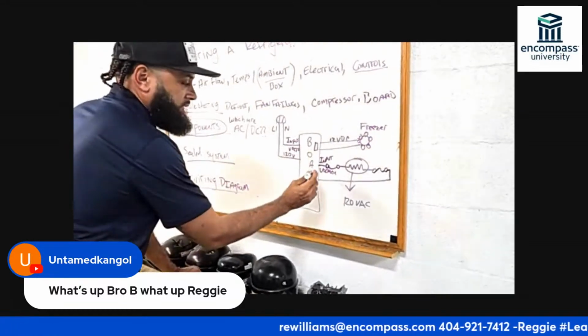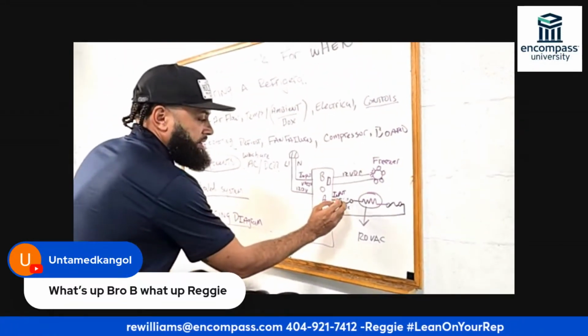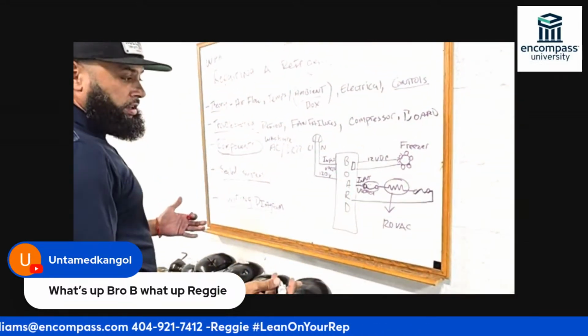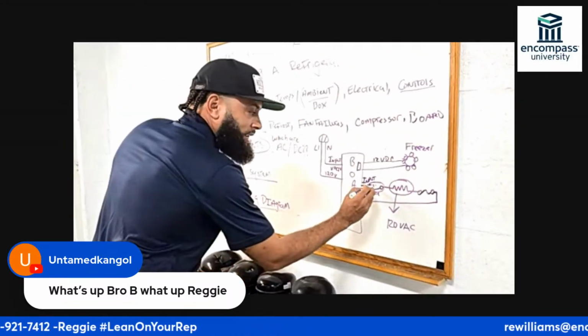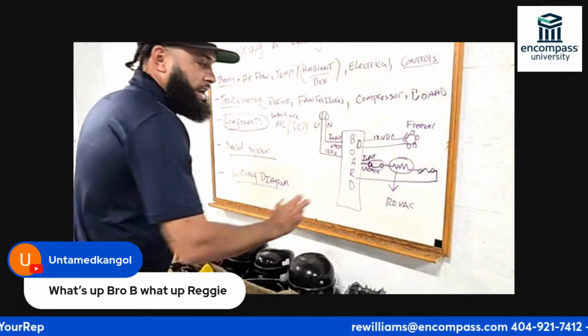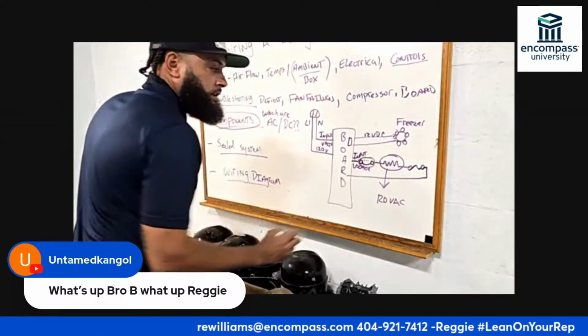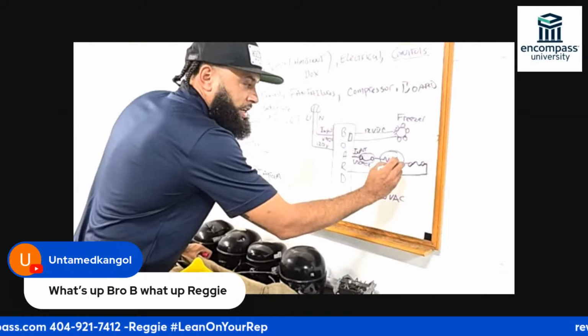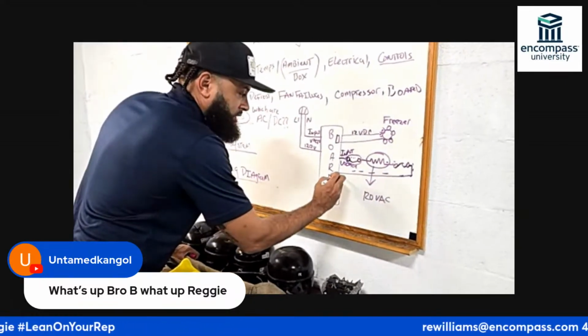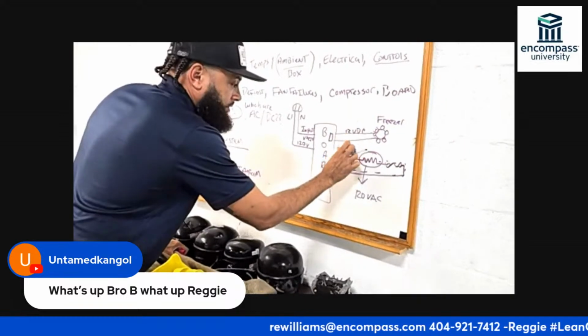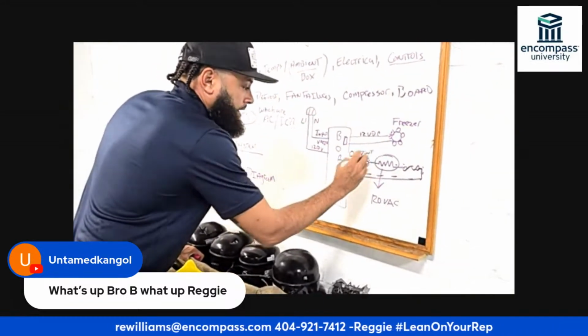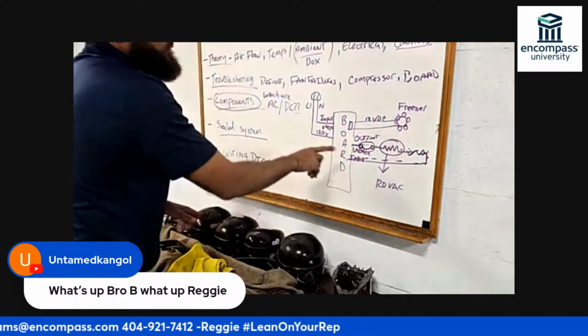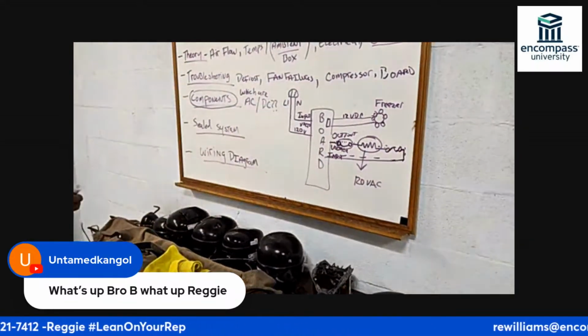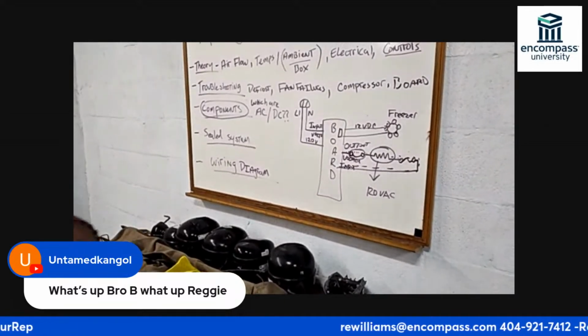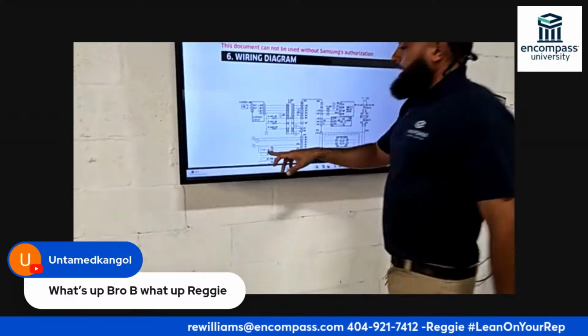In this case, you have this input voltage going through this thermostat. If it's cold and below a certain temperature, it'll allow the voltage to pass through and turn on the heater element to melt the ice off the evaporator. If the fuse is good and intact, it'll come right back. This is output, going out and then coming back. So the board sends voltage out and it comes back home. You've got to familiarize yourself with these circuits.